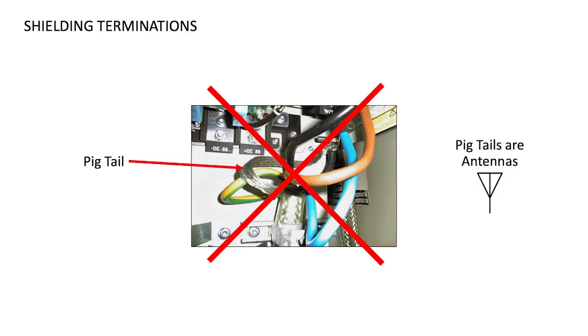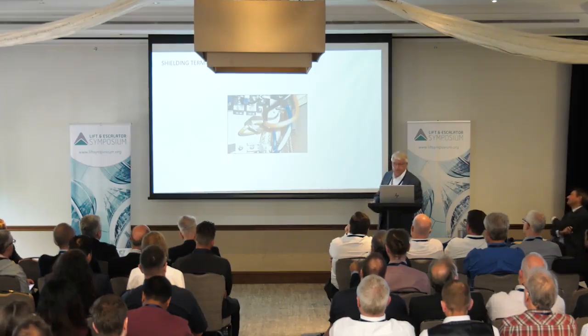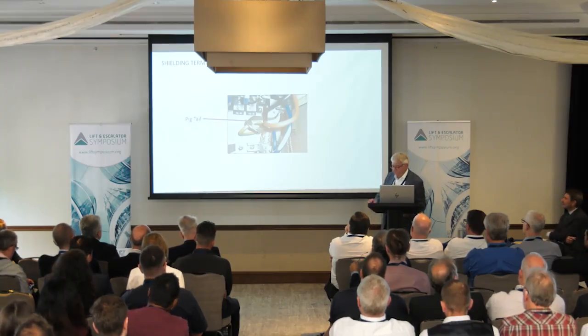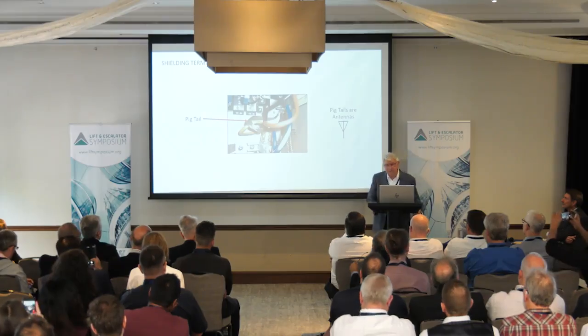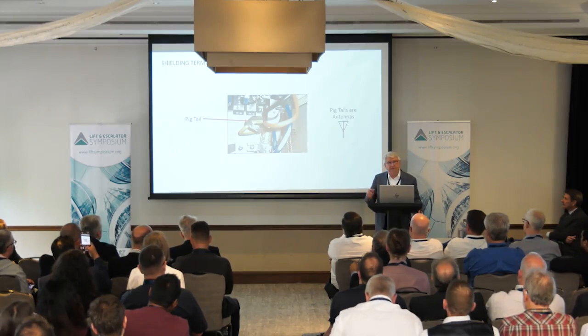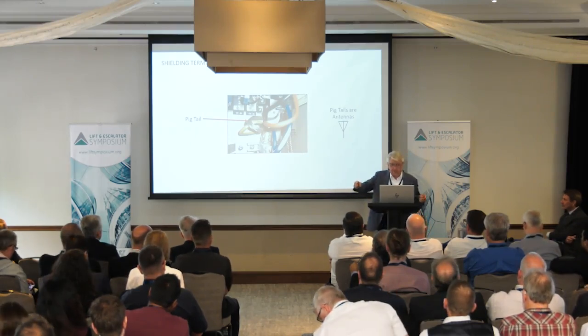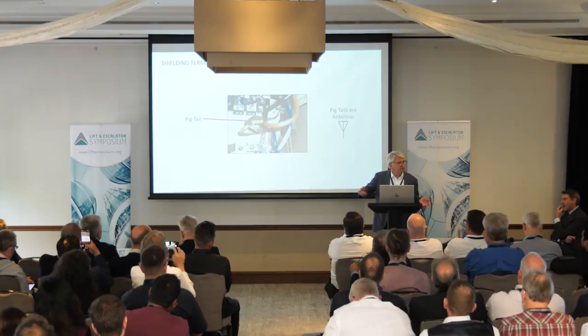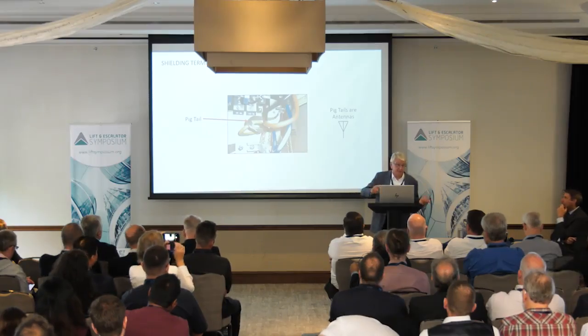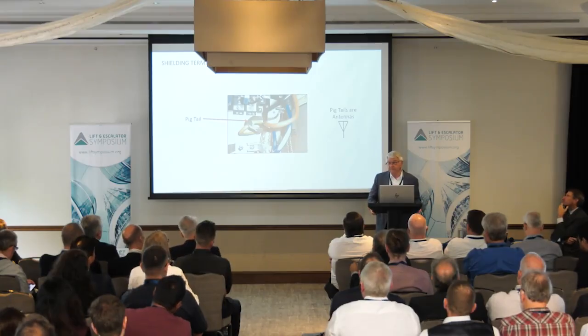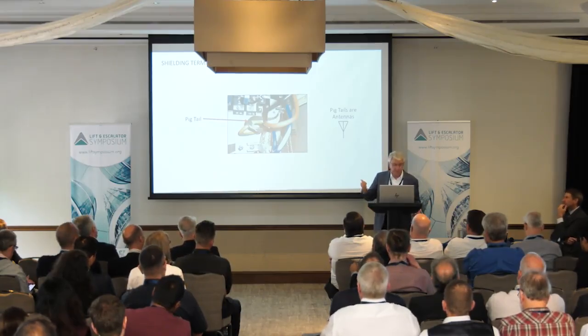And so here's an example where they strip the shielding off of the cable, make it into a pigtail, and then run that and attach that to an earthing lug. It's called a pigtail, and in reality, pigtails are a very good antenna, and so they broadcast. So you're not supposed to do that, but it's done all the time because people think in terms of continuity. Well, I've got 0 ohms here, it must be good. It's good for resistance and DC, but for AC it's quite different, and for radio frequency it's quite different. And this is typically not well done.